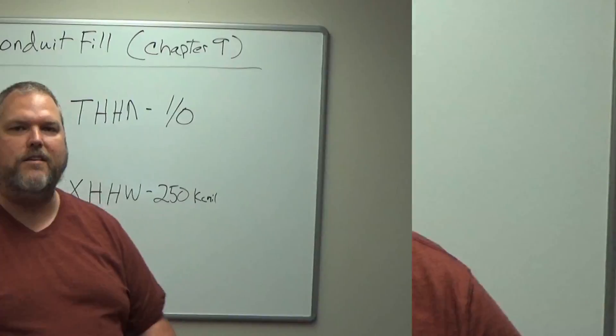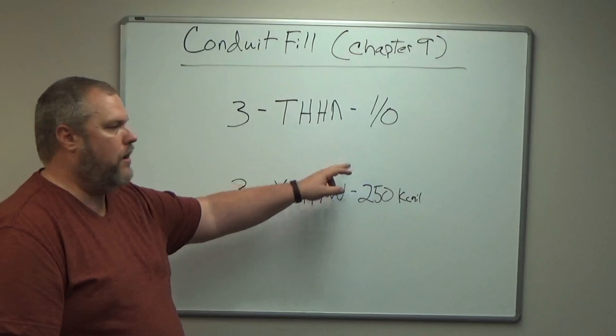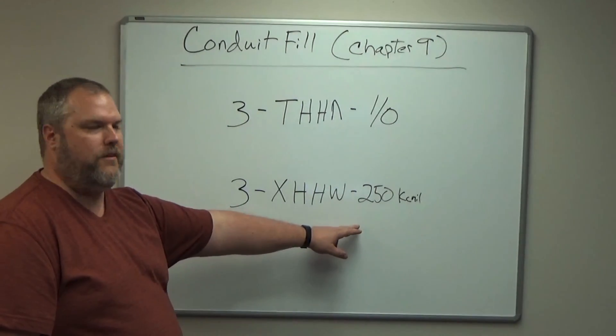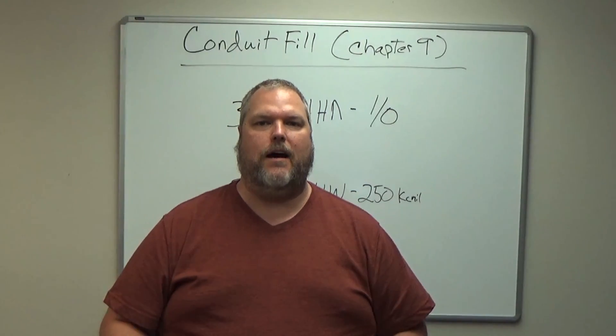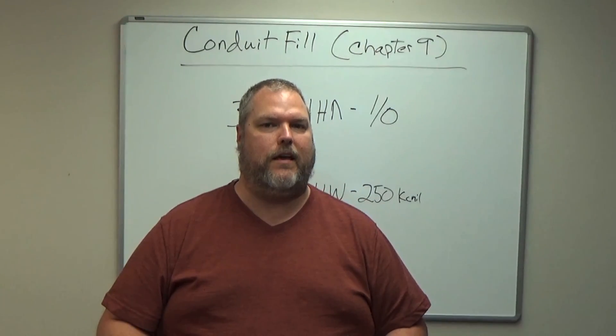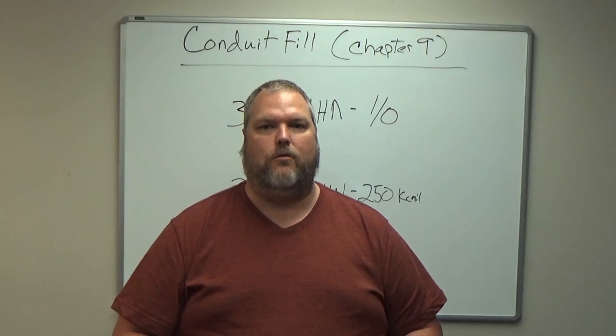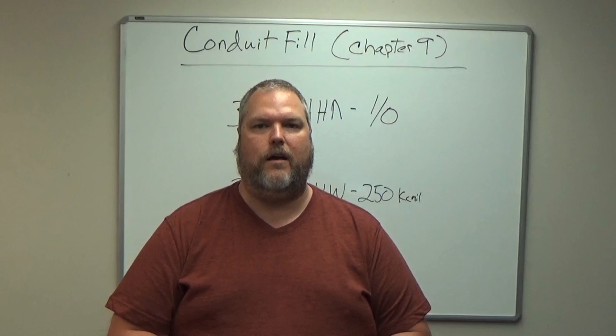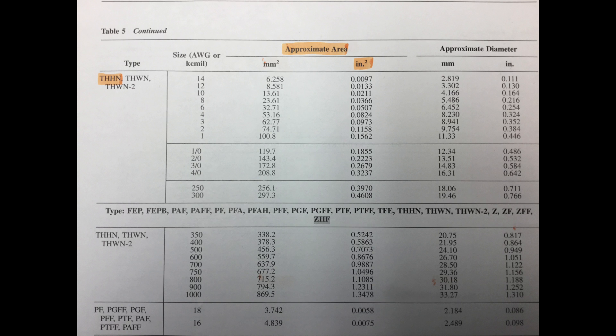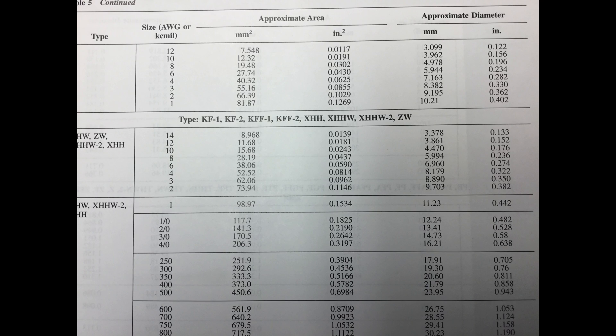Let's do an example. We're going to use three THHN 1/0 and three XHHW 250 kcmil. We're using two different types of insulation, so we have to make sure we get the correct approximate area from table 5 in chapter 9. We go into the code and check: THHN 1/0 is 0.1855 square inches, and XHHW 250 kcmil is 0.3904 square inches.